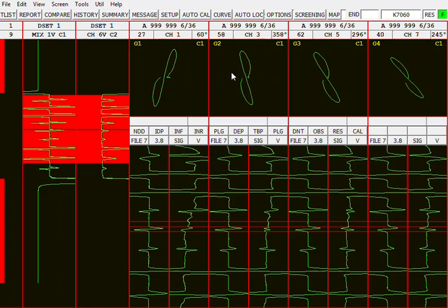So there's less phase lag. 0 degrees is on the left and 180 degrees on the right. That's kind of backwards from traditional math and trigonometry that you probably saw in school and college, high school, whatever. But 0 is on the left, 180 is on the right. Now when we step down to the next lower frequency, you have even less phase lag because lower frequencies have less phase lag. So you can see for a given flaw, this is all the same flaw, you have less phase lag with each decreasing test frequency.